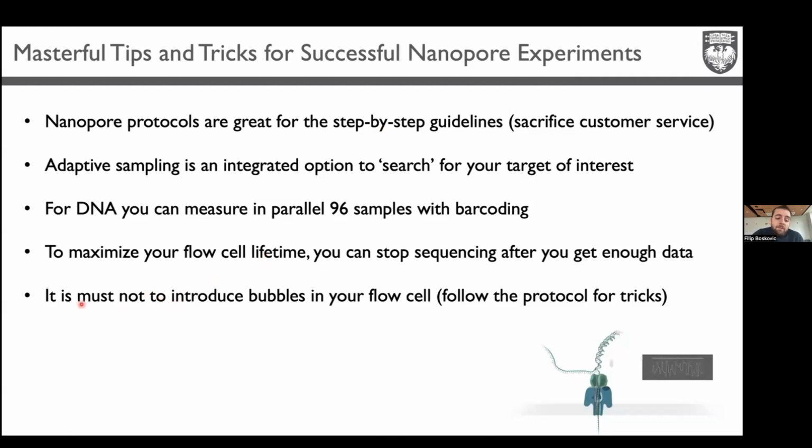Also, it is a must, and one of the most important pieces of advice written in the protocol, and I'll repeat it to you, it's crucial for your experiment and the flow cell itself: you shouldn't introduce bubbles. This is a very simple electronic measurement, but if you have a bubble, then there's no current going through the pore.